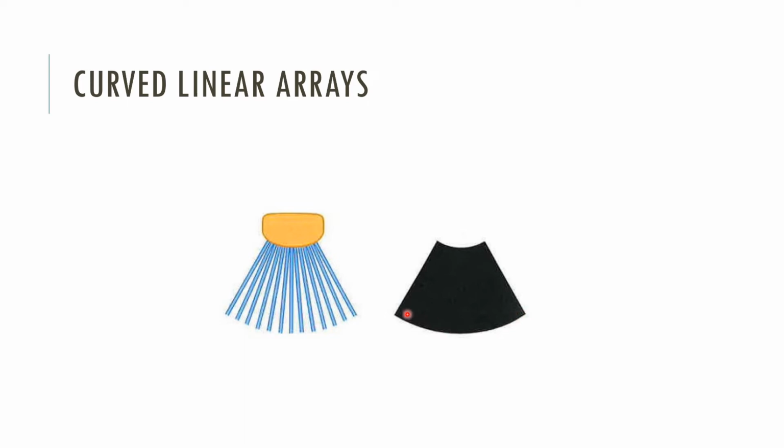But the problem with this is you can see here, when we go down to a specific depth, we start losing that lateral resolution. So the density here at the lower depth is going to be lower. So this is good imaging for specific reasons, and it gives us a larger field of view and gives us a fixed focus here. But we also lose that lateral resolution down the bottom.